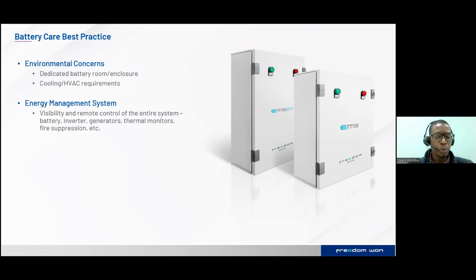Then you might need to actually lower your ambient temperature to ensure that your battery is cooled enough, so that you create conditions for best performance for the battery system. Then looking at the cooling HVAC requirements as well, we need to take into consideration the losses which the system experiences, which translate to heat generation. So we need to ensure that the HVAC system, the BTU sizing, is correct to cater for the heat losses for the particular system. Then another very important thing is the energy management system.